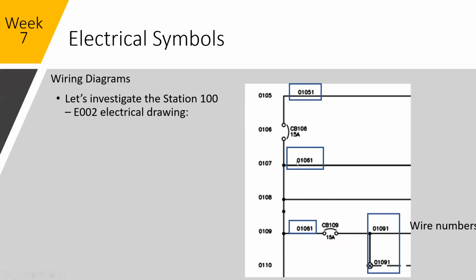Coming out of CB106, we have 01061. Well, when we come down here to line 9, we still have 01061. But on the other side of CB109, we have 01091. Now, you might ask yourself, why don't the wire numbers increment up with every line? That's because all of these are electrically the same point. So if this wire comes down to a terminal block here and a terminal block elsewhere, if you were to put your electrical meter on any of the points, you are now on the same point electrically.